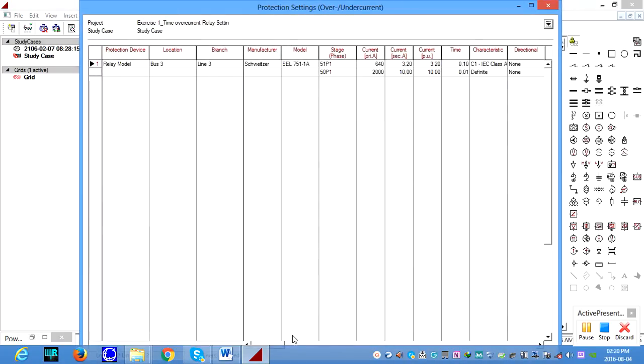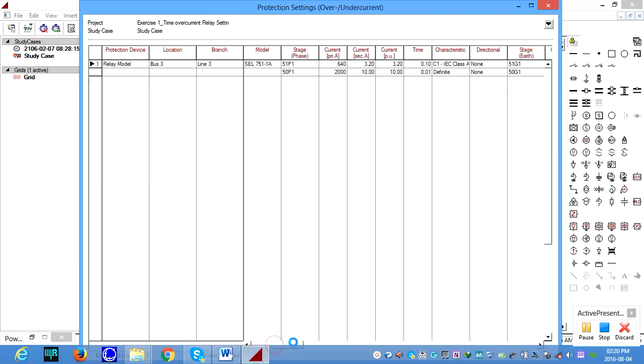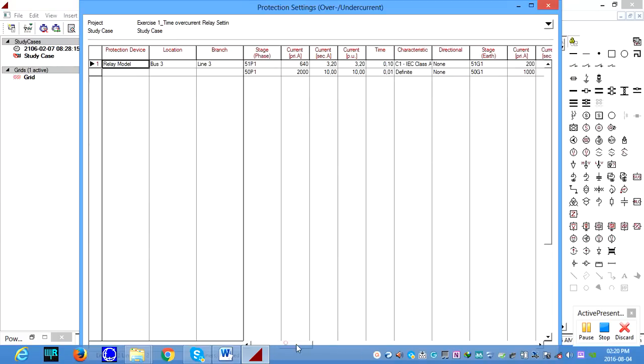Once I executed, you see, this is your protection setting, the overcurrent element. See that the overcurrent element is sitting on bus 3. It is a SEL751 relay model, and this one shows your stages. That is stage 1: you have your instantaneous 50P1 and your inverse 51P1, and the current settings in terms of primary and secondary and the time, and also the type of curve that you applied. Do you remember when we were speaking about the settings?